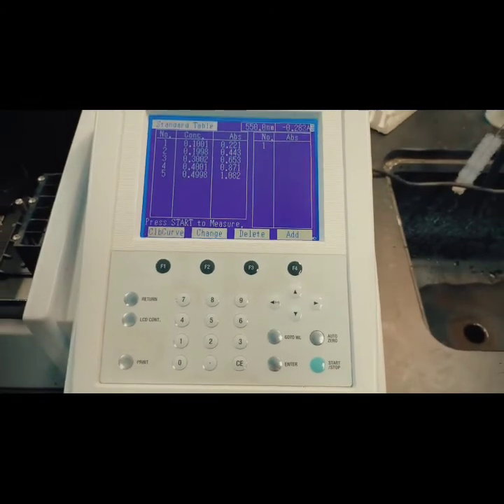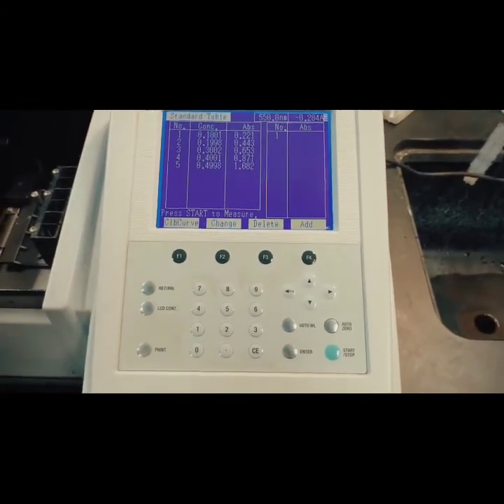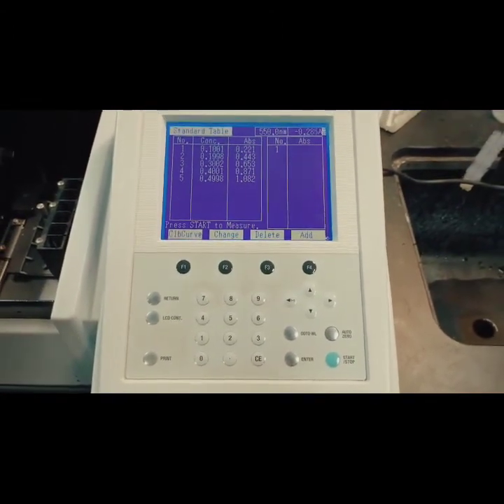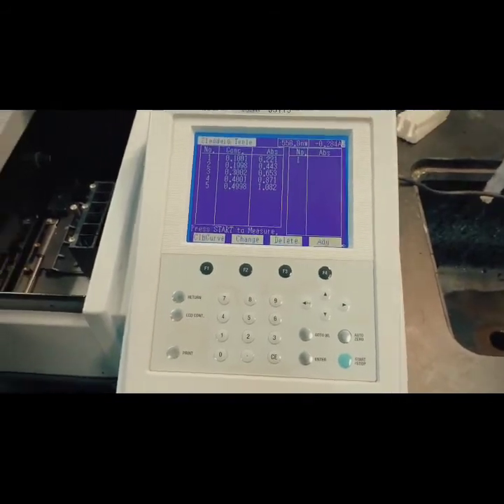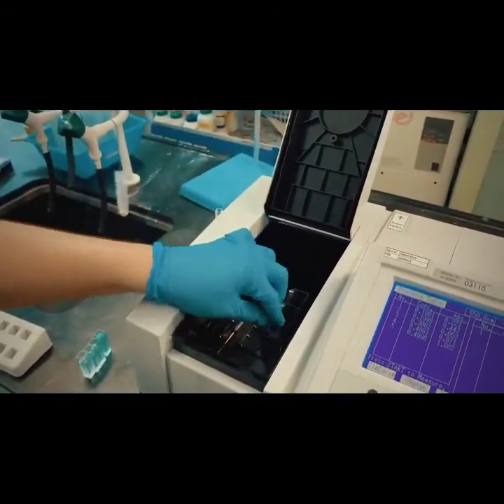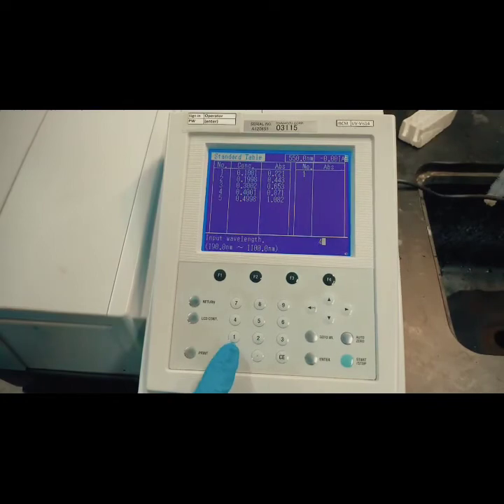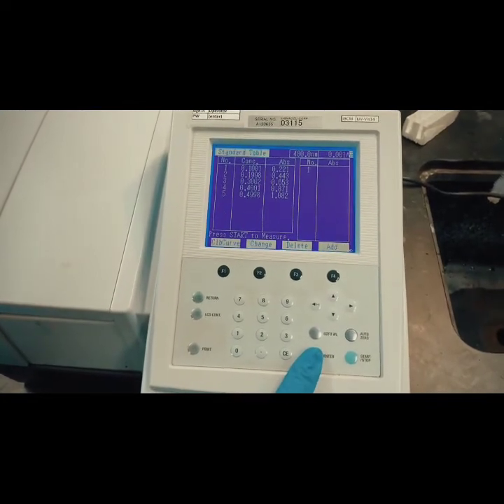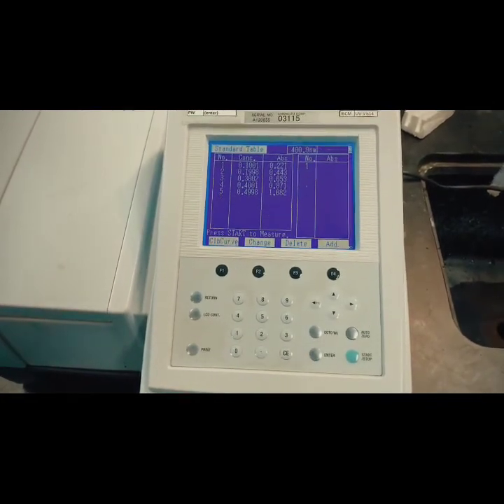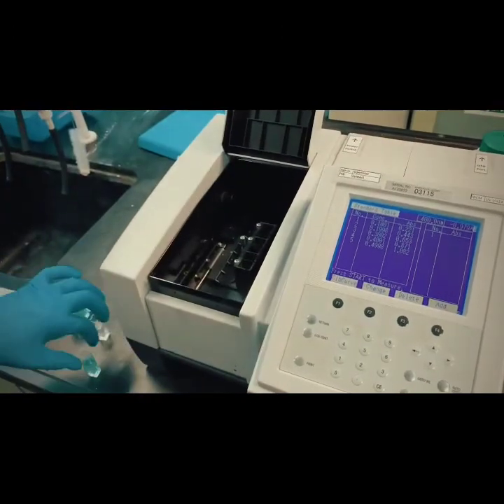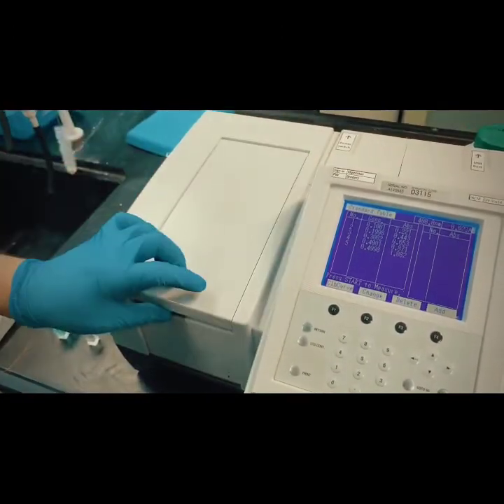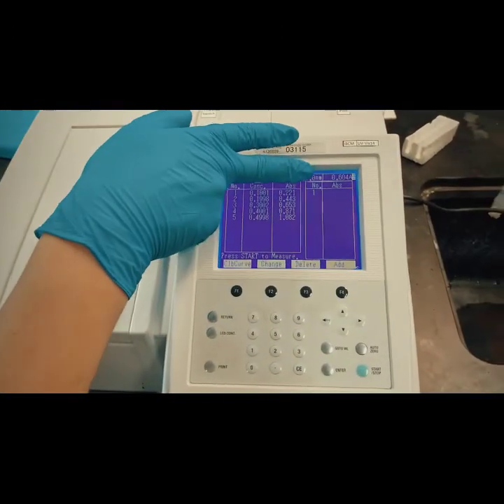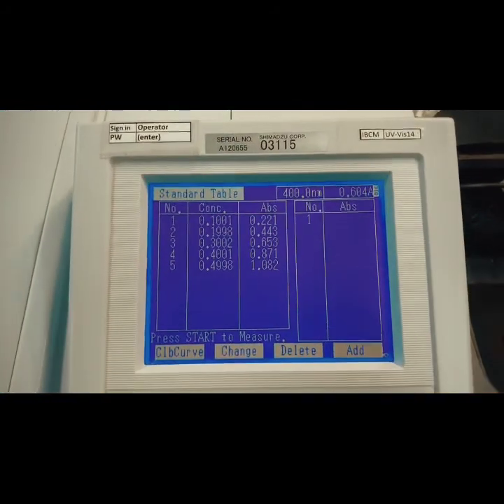The UV visible spectrophotometer may also be used to find the absorbance of an unknown sample. To calibrate the machine, place a blank cuvette in the machine, select Go to Wavelength, and select the desired wavelength. Then select Auto Zero to calibrate the machine. Replace the blank cuvette with a cuvette containing the unknown sample, and the absorbance value will be shown on the top right of the screen.